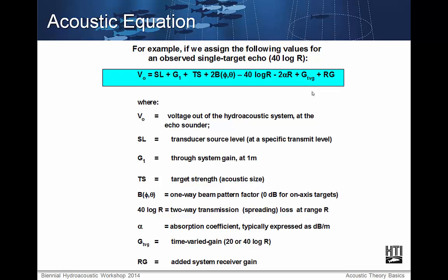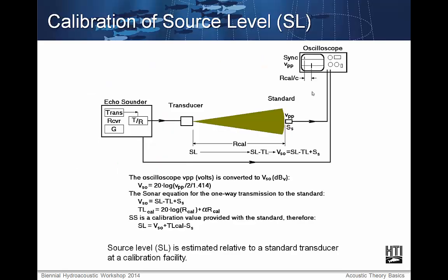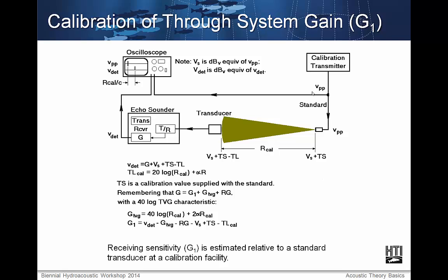The only factors not yet discussed are the through system gain and the source level of the instrument. Both are derived during calibration procedures from the manufacturer. The source level is estimated relative to a standard transducer at a calibration facility, and the receiving sensitivity is also estimated there. HTI does both of these calibrations and recommends a yearly recalibration. However, if great care is taken during sphere calibrations in the field, yearly calibrations at HTI may not be required.